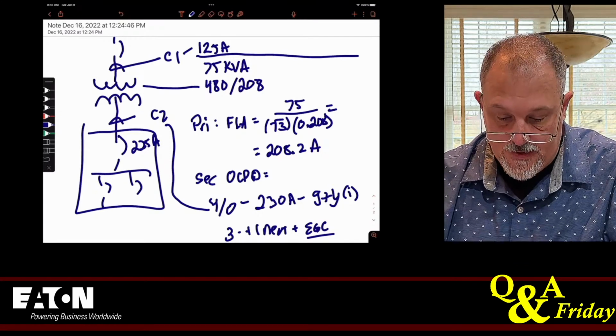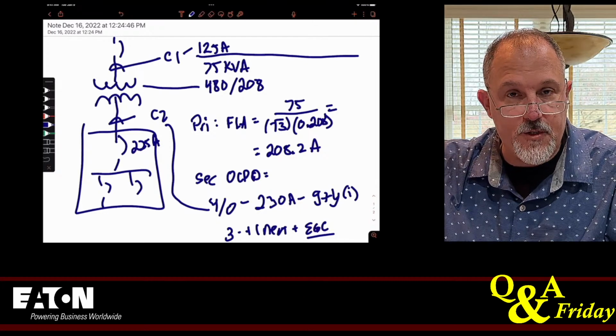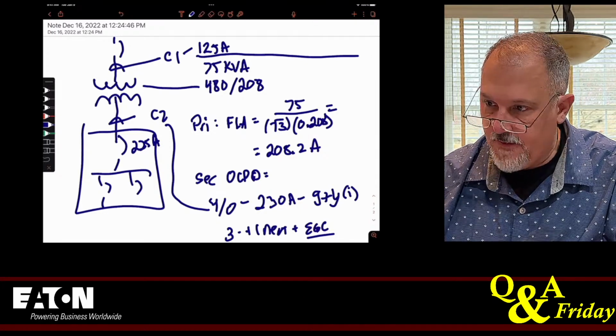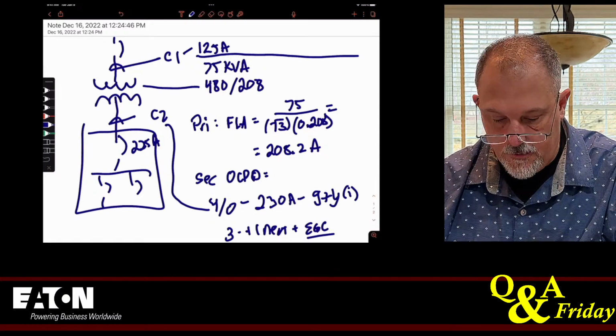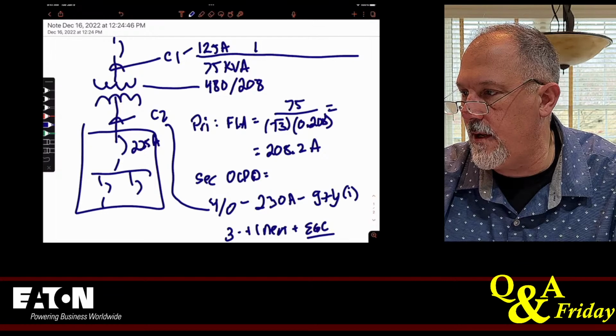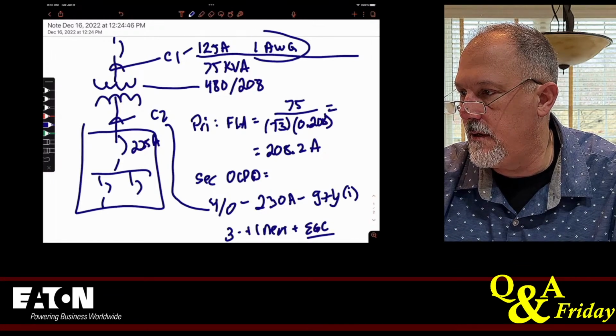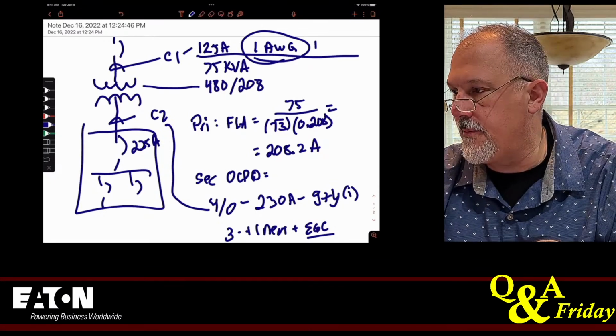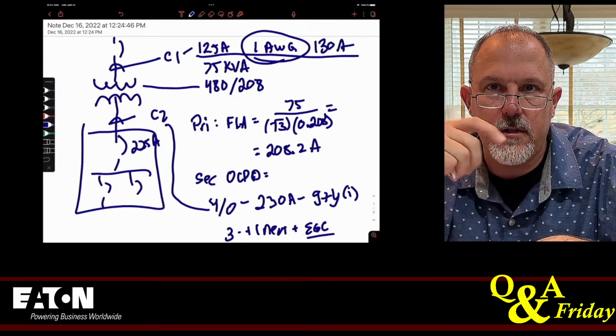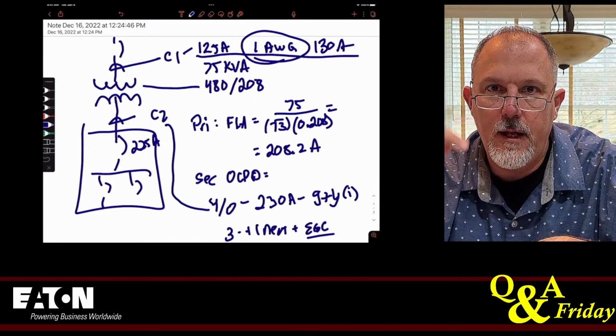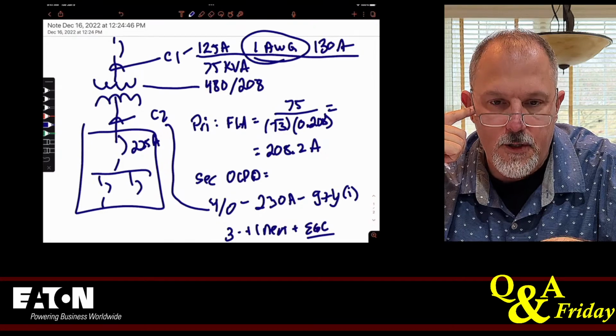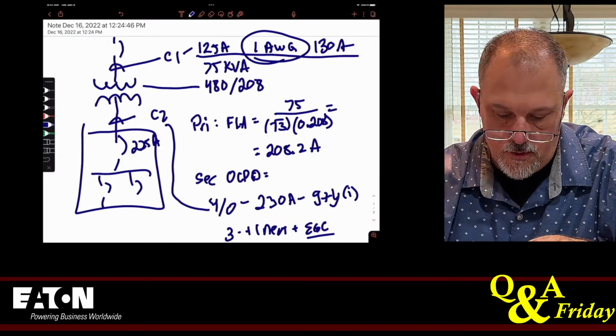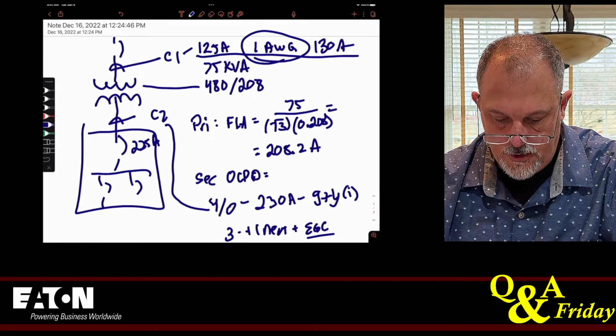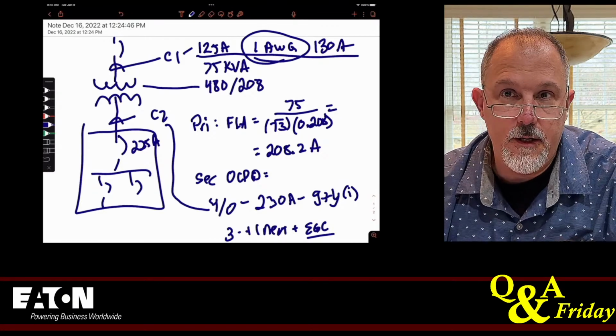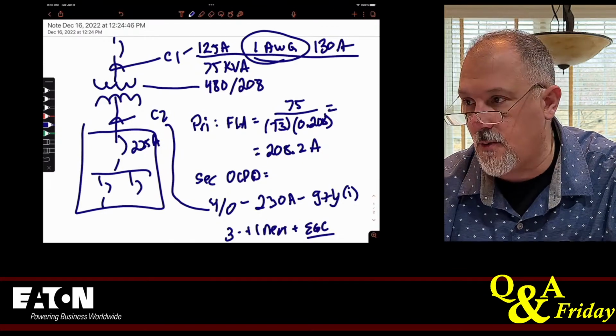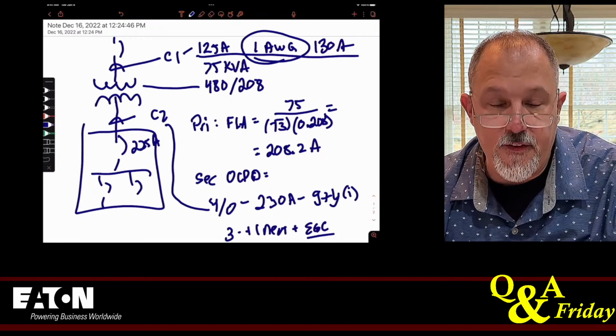For 125 amps, we've got to use the 75 degrees C column because I'm going to be coming out of a piece of equipment upstream that's 75 degrees C. And if I need 125, I could use a number one American wire gauge right there. That'll give me 130 amps. Now that'll be 3 conductors, no neutral because it is a delta primary, and an equipment grounding conductor. So 3 conductors. I'd use a 1 gauge. You can use a 1/0 if that's what you've got on the truck. Still put the same overcurrent protective device, 125 amps, because a 1/0 will get you 150 amps.